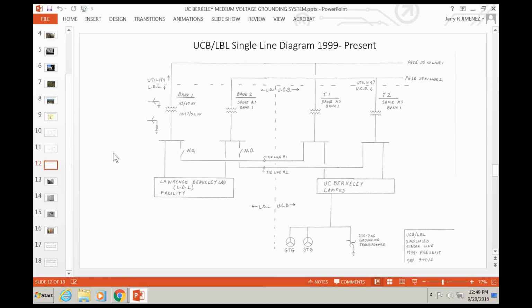I'm not very knowledgeable about resistance grounded systems, but one thing I was wondering is, have there been instances when you have low-level faults perpetuating for a long period of time? I would say no. My experience, not just here, but at my prior job, was on 12 kV. If there's a fault, it's going to go to the maximum level pretty quickly. 12 kV has just so much potential behind it that it doesn't tolerate much. In my experience, it doesn't tolerate much with intermittent faults or faults that only bleed a few amps. Every time I've encountered a ground fault, it goes fairly quickly. That makes sense. So basically, at this voltage level, when you have a fault, you know it, and it's that simple. Yes.